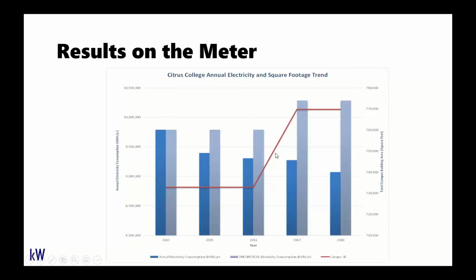So actually around 2016-17, Citrus built a new building and increased the square footage of their campus. And this light blue line in the bar here is showing, if the campus had maintained the same energy intensity that they were operating at prior to our retro commissioning work, what the campus energy consumption would have been with that added square footage. And as you can see, even though the campus increased in size by about 5%, we were able to achieve an overall reduction in energy consumption of 7% compared to the previous baseline, or around 10 or 15% compared to what would have been the case with that increased square footage.